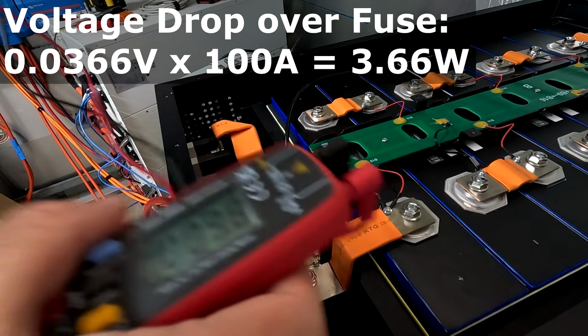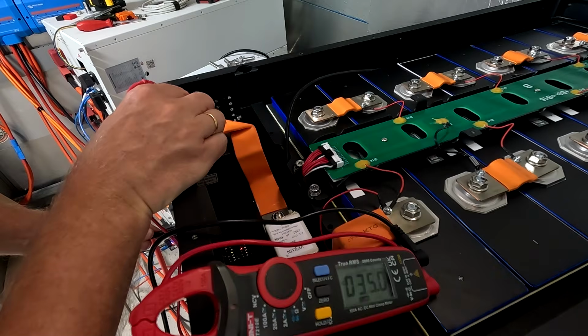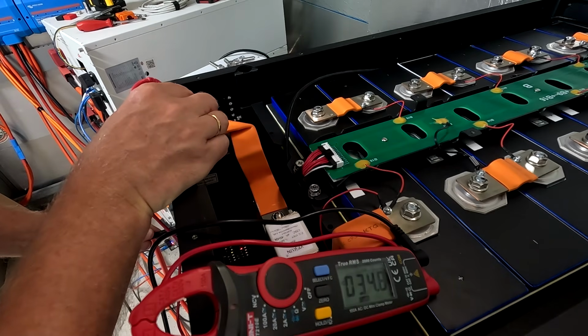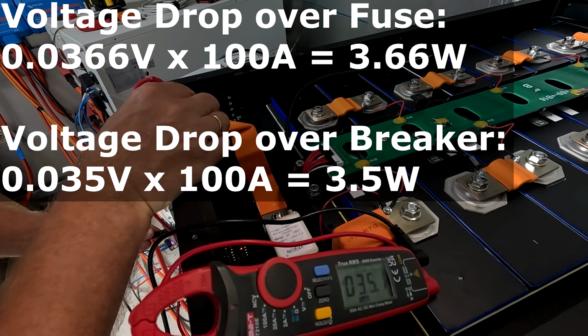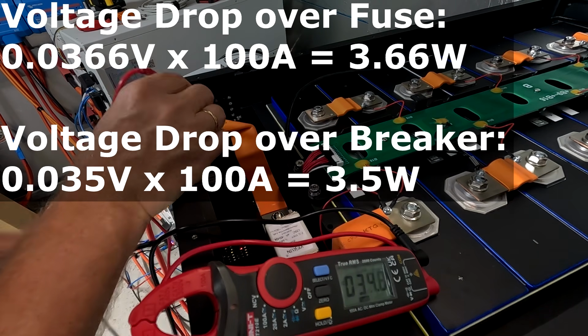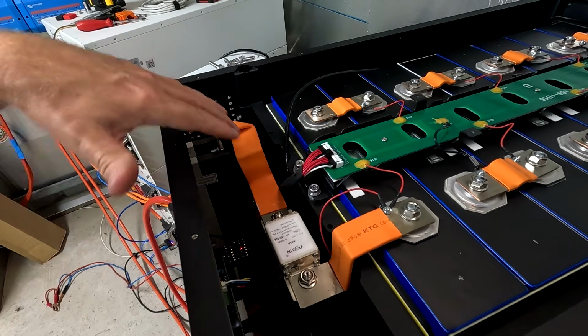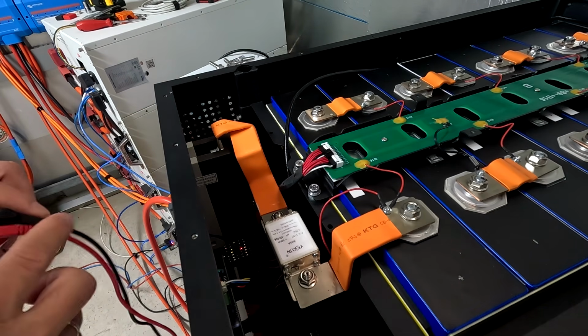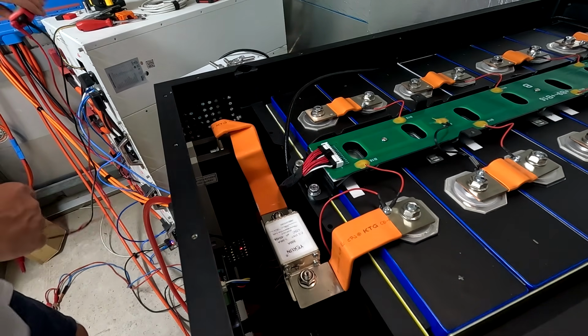Let's do the same here on the breaker. 35 millivolts, so the same. So 3.5 watts of loss on the breaker plus another 3.5 on the fuse makes 7 watts total loss on these two devices at 100 amps.